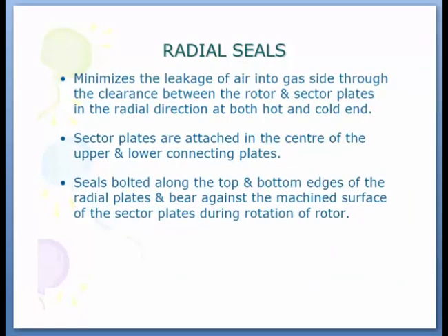Now we will see what is the purpose of providing radial seals. It minimizes the leakage of air into the gas side, as we had discussed earlier. The air side has more pressure in comparison with the gas side, through the clearance between the rotor and sector plates. In the next slide we will see the positioning of rotor and sector plates in the radial direction at both the hot and cold end.